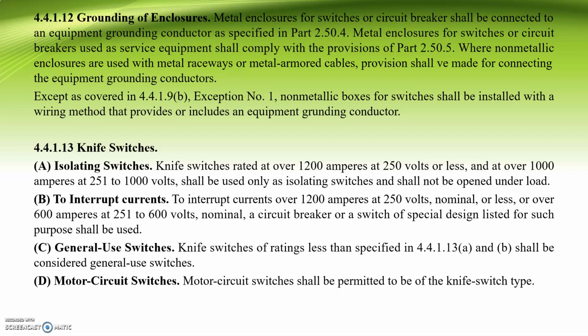So chapter 4.4.1.12, grounding enclosures. So metal enclosures for switches or circuit breakers shall be connected to an equipment grounding conductor as specified in part 2.50.4. So metal enclosures for switches or circuit breakers used as service equipment shall comply with the provisions of part 2.50.5. Where non-metallic enclosures are used with metal raceways or metal armored cables, provision shall be made for connecting the equipment grounding conductors, except as covered in chapter 4.4.1.9b, exception number 1. Non-metallic boxes for switches shall be installed with a wiring method that provides or includes an equipment grounding conductor.